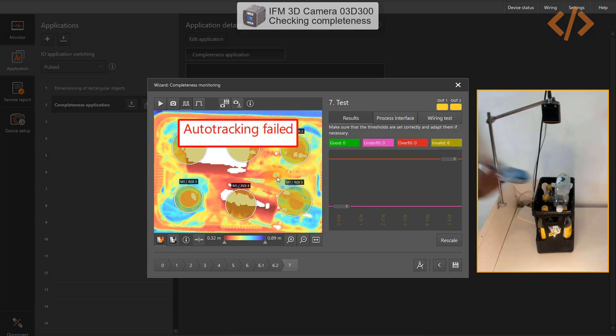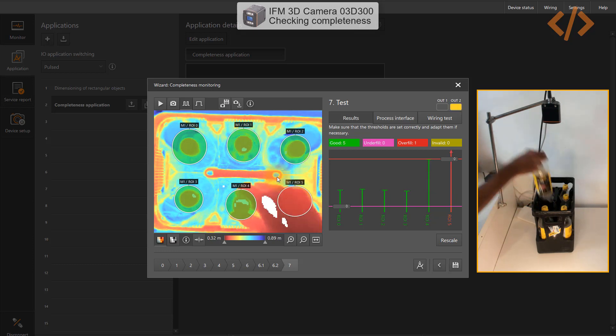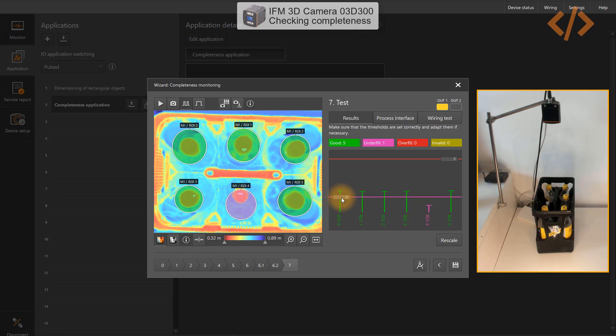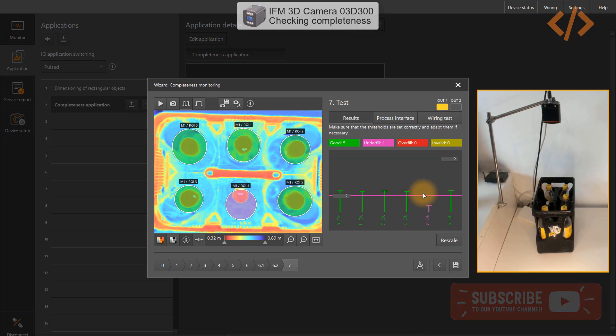Interestingly, if I remove one bottle from the container and put a small bottle inside, the camera initially still detects ROI 4 as filled because the small bottle is still within the area of measurement. If I position it differently, ROI 4 reads as empty. So you can recalibrate the measurements to define what counts as good state versus bad state. If the measurement threshold requires a minimum height, the smaller bottle will be flagged as underfill — allowing you to detect if the correct bottle is in the container.